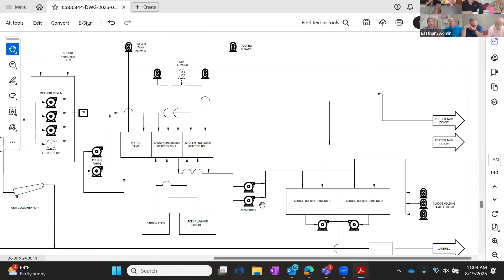Downstream of the SBRs, you're going to discharge into a post equalization tank. That post equalization tank will then pump to the cloth media disc filters. Having that post equalization tank allows us to reduce the size of the downstream unit processes. With an SBR, it's a batch process, because they decant at a high rate. The flow goes into the SBR at a relatively low flow rate, does its biological process, settles, and then you decant clear water off the top. During that decant cycle you could be on the order of 1,000 gallons per minute on the decant, while you might be filling at 100 GPM. So by sizing that EQ tank downstream, we can keep the downstream unit processes much smaller. Otherwise, we would have to size them to handle the peak decant rate.